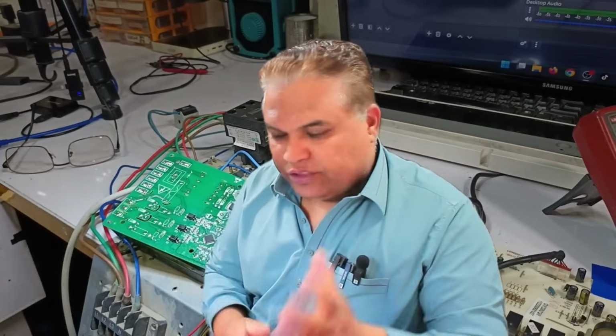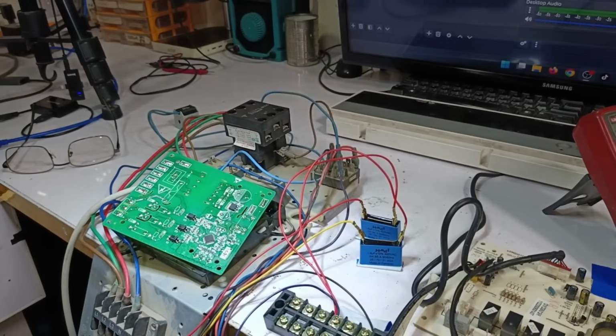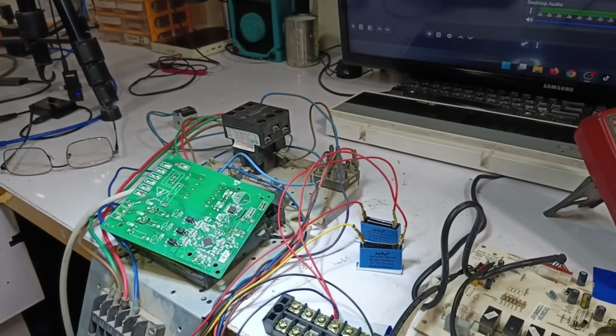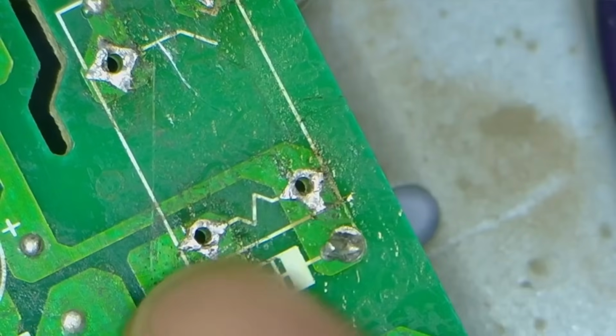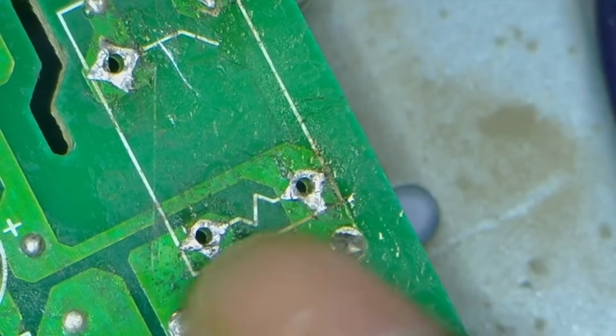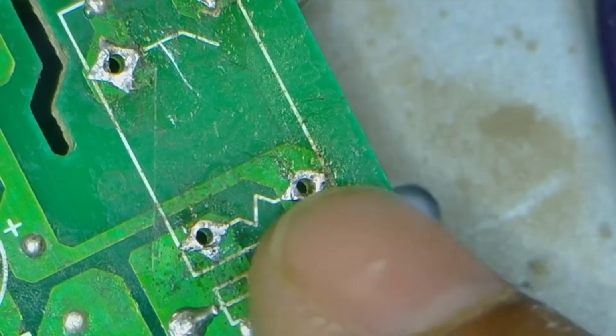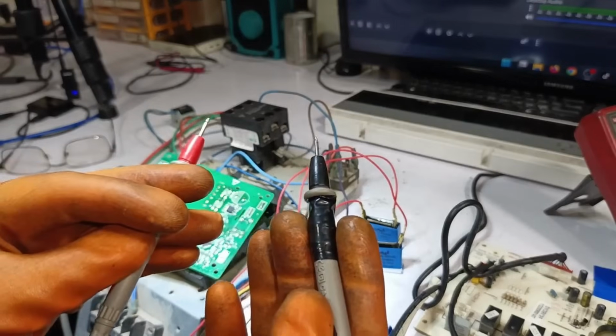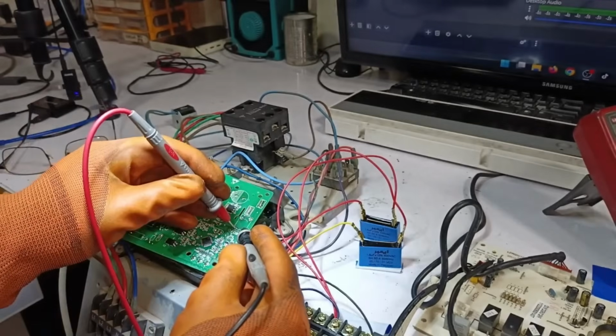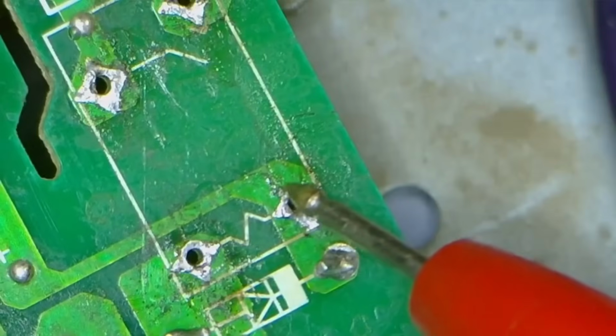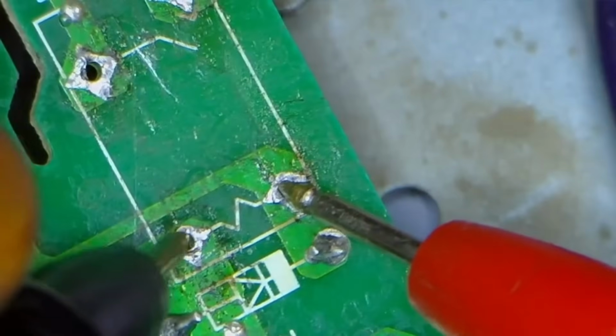For this, we will once again supply power to the system, and as soon as the electricity is supplied, we will begin testing. As you can see, I have already removed the relay, and we will now measure the voltage at the points where we expect to find around 12 to 14 volts. Let me explain how we will do it. We will connect the two probes of the multimeter, the positive probe to the positive side, and the negative probe to the negative side. This test will give us a good idea of what's happening.